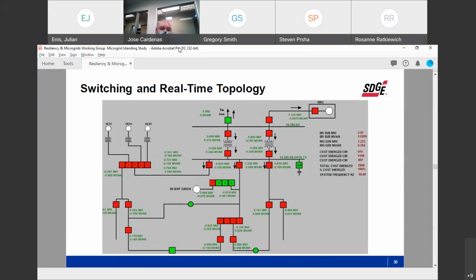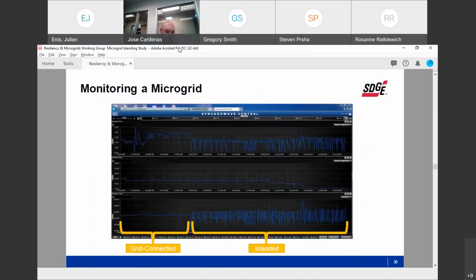So it's important that you have section line devices in the field to make sure you are successful when you do that load step. If you have too much load between your isolating devices, you could easily drop the load, frequency could go out of bounds, and then you can drop the whole island. So that's an important consideration. Make sure you have the appropriate isolating devices in the field to sectionalize your load to make sure you're successful. Okay, I think we'll go on to the next slide, please.